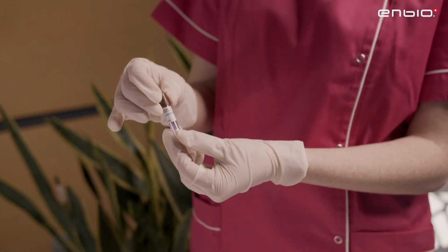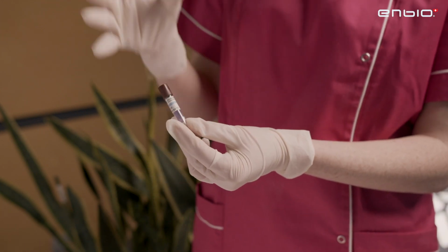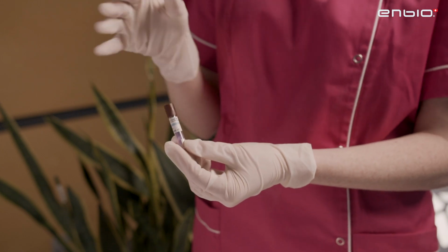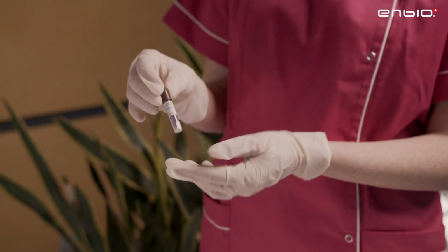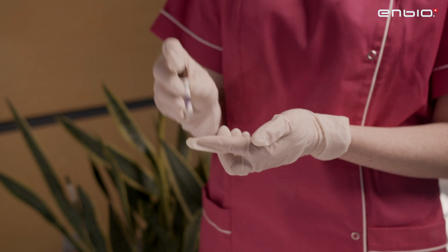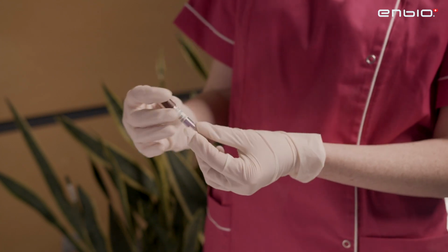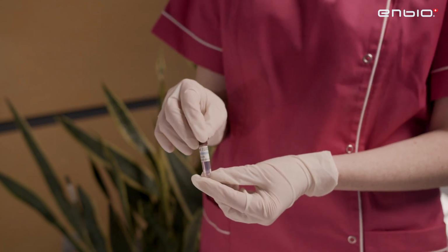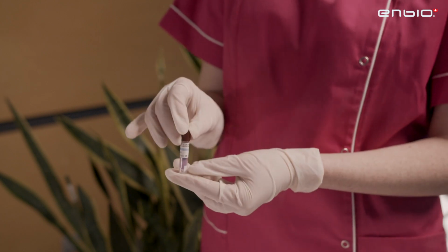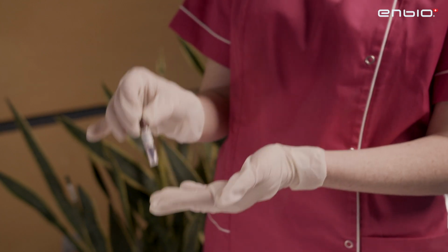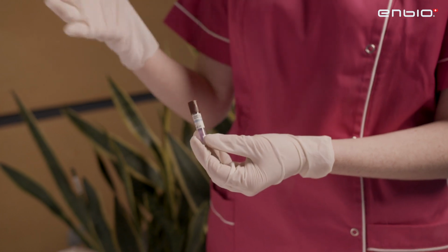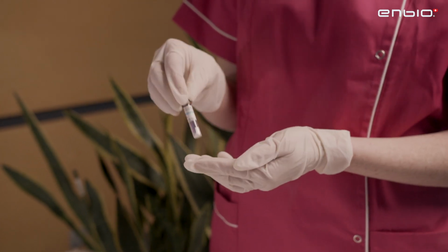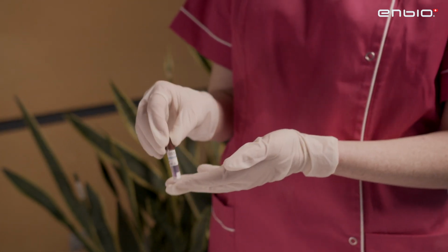And this other biological test, the EZ test, has the same purpose, to see if all the spores were removed. And in order to check the efficiency of the sterilization process in this case, we need a special device, an incubator. And if we have it in our salon, it means that we don't have to go to the laboratory. We can check the results in the salon with that incubator.